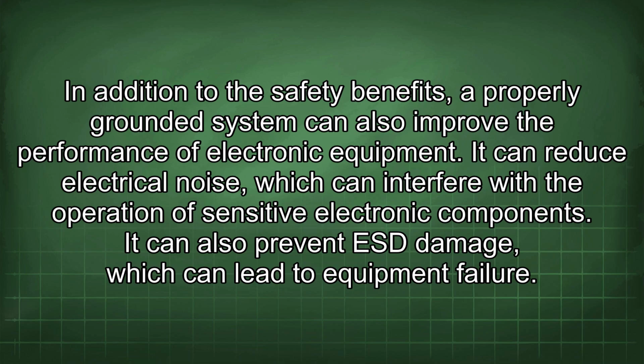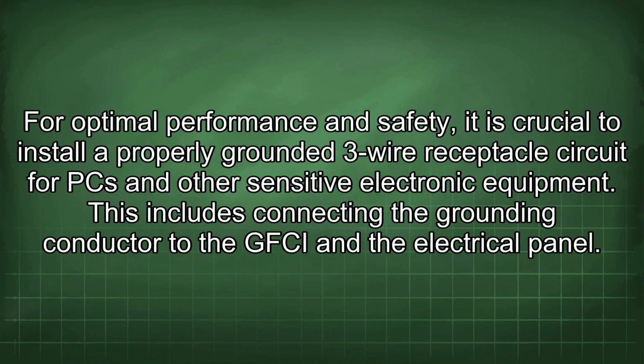In addition to the safety benefits, a properly grounded system can also improve the performance of electronic equipment. It can reduce electrical noise, which can interfere with the operation of sensitive electronic components. It can also prevent ESD damage, which can lead to equipment failure. For optimal performance and safety, it is crucial to install a properly grounded 3-wire receptacle circuit for PC and other sensitive electronic equipment. This includes connecting the grounding conductor to the GFCI and the electrical panel.